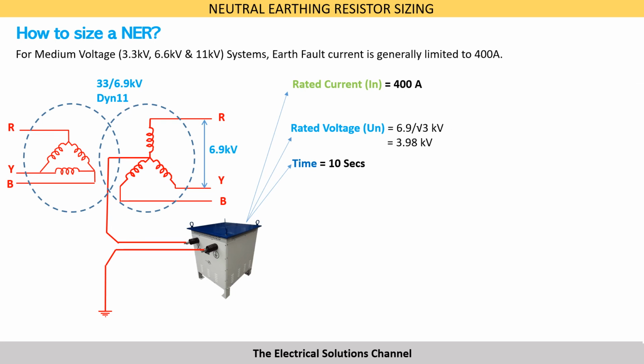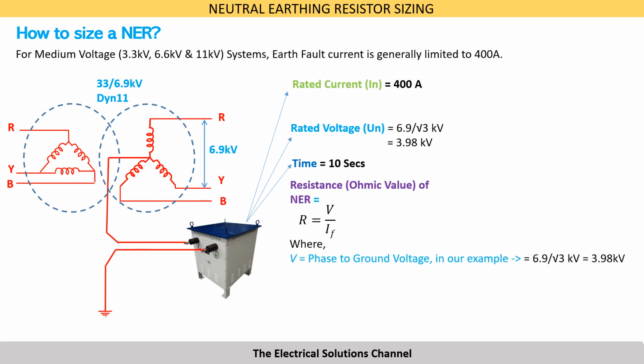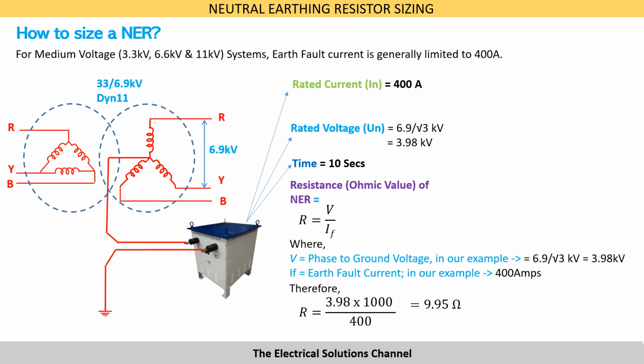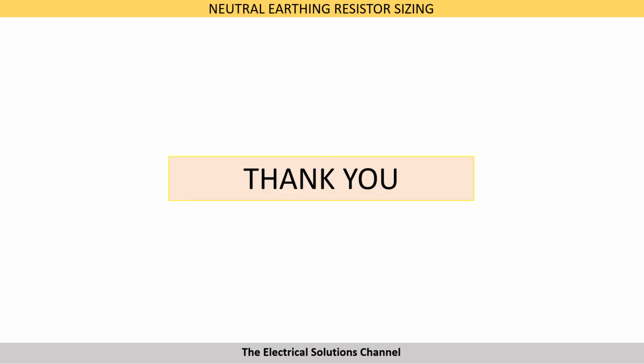Let us now try to understand how to calculate the ohmic value of the NER. The ohmic value of the NER is given by the formula R is equal to V by IF, where V is the phase to ground voltage. In our example, this is equal to 3.98 kV. And IF is the earth fault current, which in our example is 400 amps. Therefore, ohmic value of the NER is equal to 9.95 ohms. This concludes my video on NER sizing.